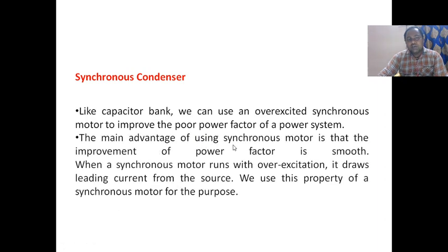The main advantage of using a synchronous motor is that the improvement of power factor is smooth, not rough. When the synchronous motor acts as a synchronous condenser, the motor is not operating any load, that is, a no load condition under over excited condition.